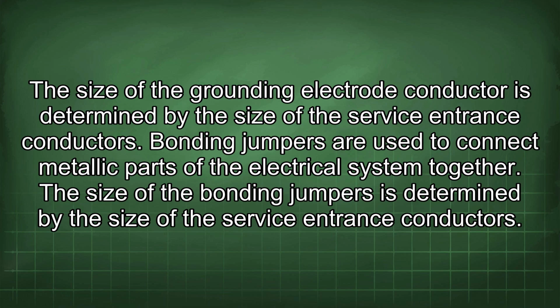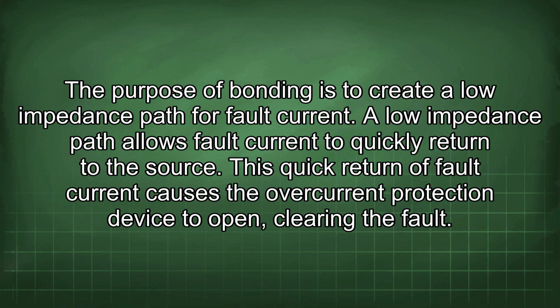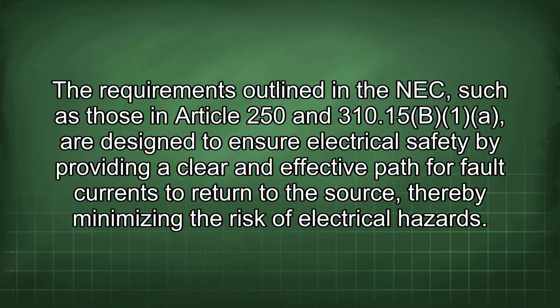Bonding jumpers are used to connect metallic parts of the electrical system together. The size of the bonding jumpers is determined by the size of the service entrance conductors. The purpose of bonding is to create a low impedance path for fault current. A lower impedance path allows fault current to quickly return to the source. This quick return of fault current causes the overcurrent protection device to open, clearing the fault. The requirements outlined in the NEC, such as those in Article 250 and 310.15, are designed to ensure electrical safety by providing a clear and effective path for fault currents to return to the source, thereby minimizing the risk of electrical hazards.